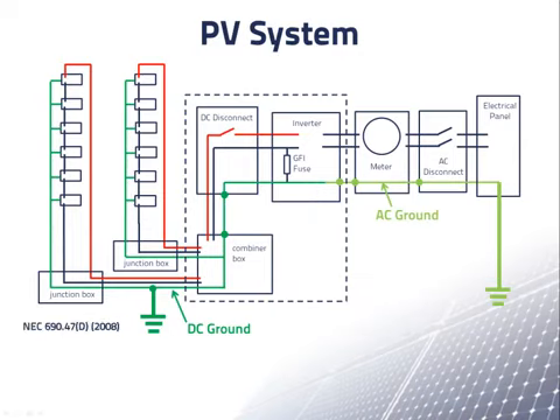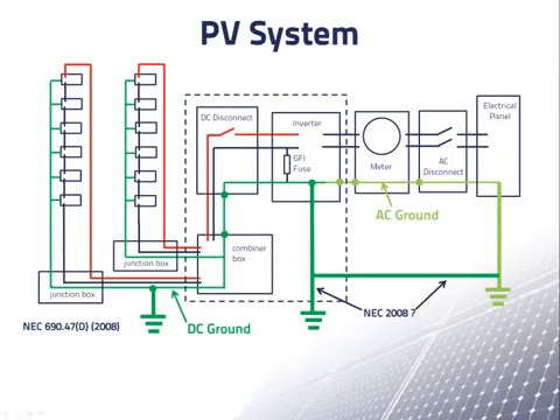In the 2008 version of the NEC, a direct connection is specified between the DC ground and a grounding rod, as close as possible to the array. This makes sense for a ground-mounted array away from the building, but is less practical for an array on a roof. If the array is on a roof, it is unclear whether the requirement is met with a direct wire to a grounding rod from where the DC and AC grounds meet in the inverter. If it is acceptable, a connection to the building's existing ground might also do. Both of these are subject to interpretation. With this lack of clarity, much of the requirement depends on the decision of the local electrical inspector.